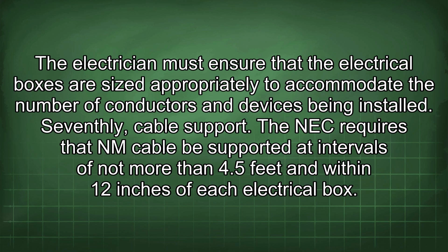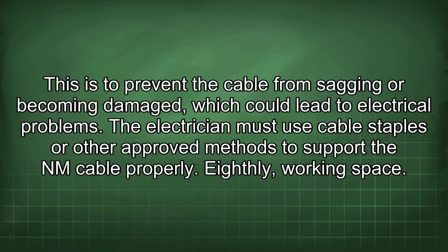feet and within 12 inches of each electrical box. This is to prevent the cable from sagging or becoming damaged, which could lead to electrical problems. The electrician must use cable staples or other approved methods to support the NM cable properly.